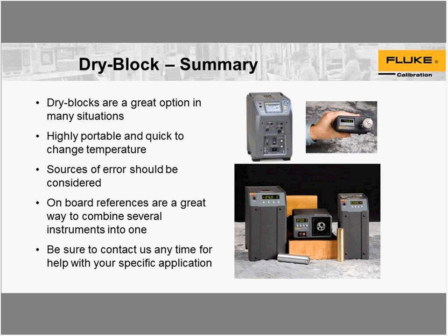In the example here, I'm referencing my 9140 series field metrology well, where we've combined a heat source, a reference, and inputs for UUTs all into one unit. So again, we're trying to create time savings and equipment savings by implementing it into a single unit.